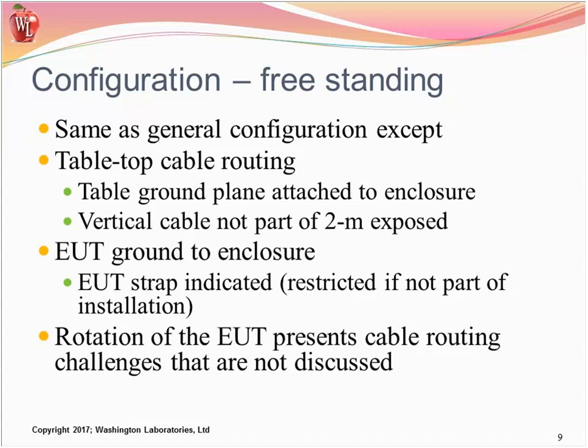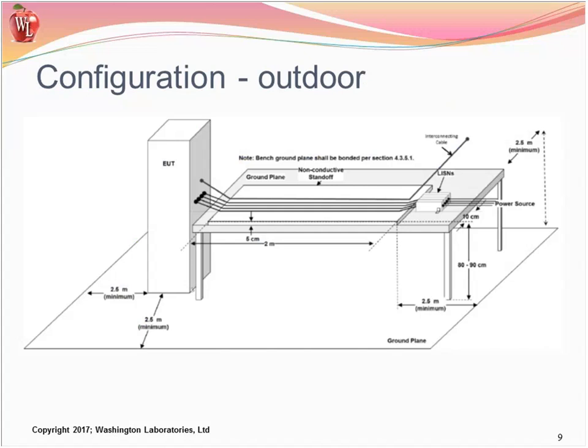And the rotation of the EUT presents some cable routing challenges, but that's not discussed. Remember, I need to turn this thing around for maximum exposure. And that's not just for the conducted test or the radiated test. We need to configure it that way so coupling can be portrayed. For an outdoor configuration, we have a similar thing to the tabletop, except suddenly the cables look like they come out the side, but they could be coming out the top or the bottom or wherever they need to egress out of the freestanding configuration.